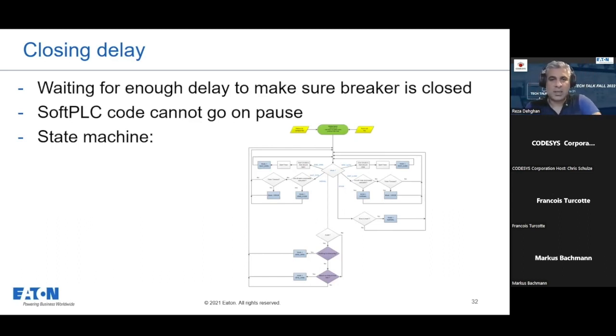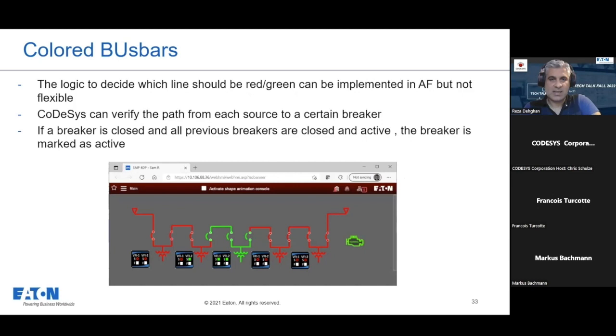Next. Yeah. Another thing that was asked by the transformer team was the ability to have, on the HMI single line diagram, lines that are energized or not energized in different colors. The logic to decide which line should be red or green can be implemented in an automation function, but it's not flexible. Again, as I said, with an automation function, first of all, it's not flexible and it's much more complex.